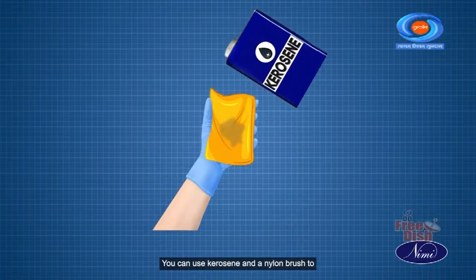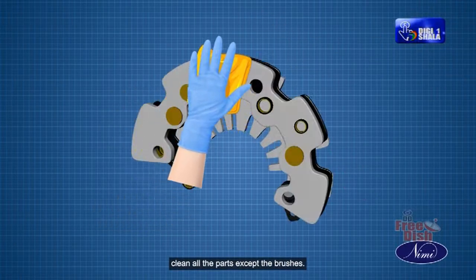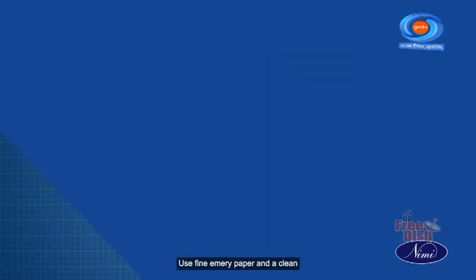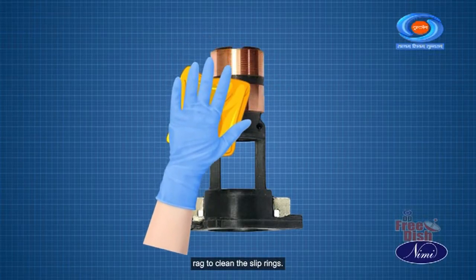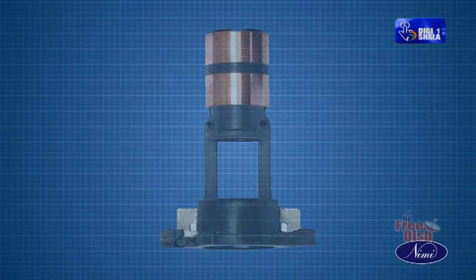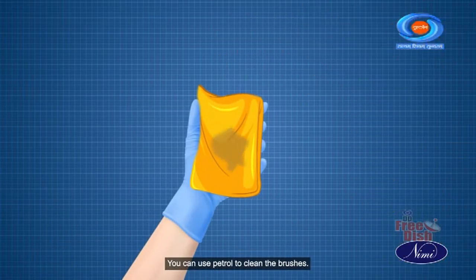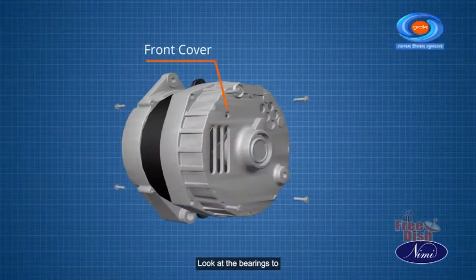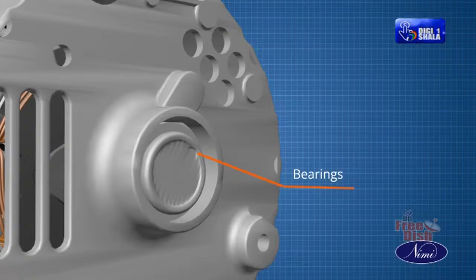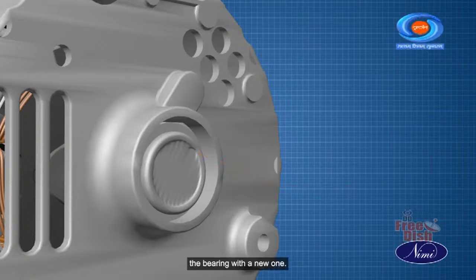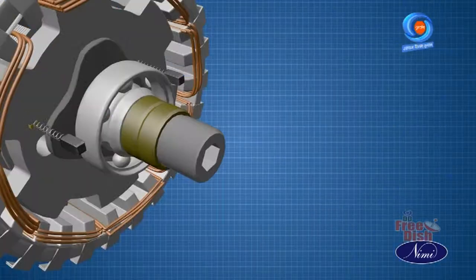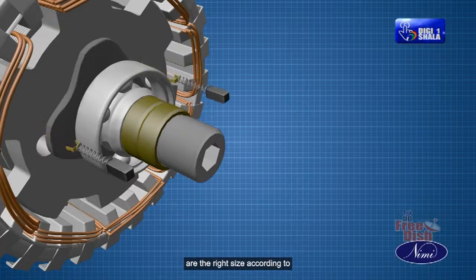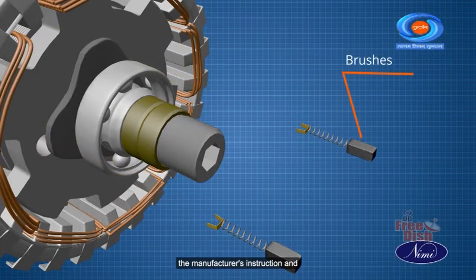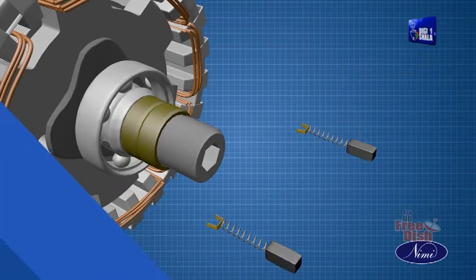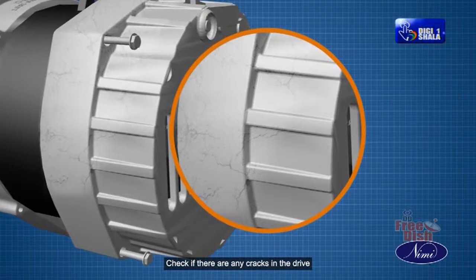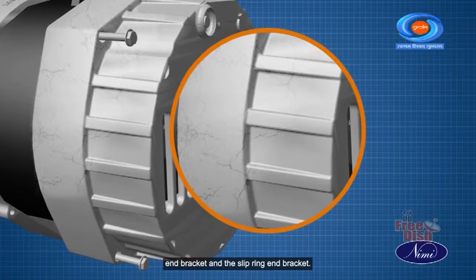You can use kerosene and a nylon brush to clean all the parts except the brushes. Use fine emery paper and a clean rag to clean the slip rings. You can use petrol to clean the brushes. Look at the bearings to see if they are broken. If you need to, you can change the bearing with a new one. Check the brushes to make sure they are the right size according to the manufacturer's instruction and replace them if they need to be. Check if there are any cracks in the drive end bracket and the slip ring end bracket.